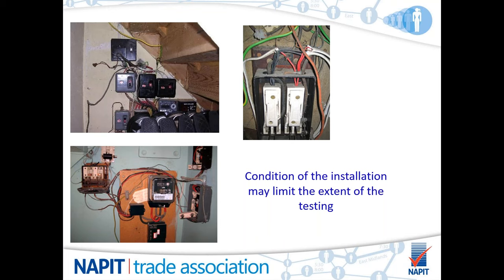Once again, the condition of the installation may limit the extent of the testing that you wish to carry out. As you can see from the pictures in this slide, the use of connector block for the installation, there's exposed conductive parts, like we spoke about before, meter tails have not been secured, which again could lead to loose connections and potential burning. And also, in the top right picture, we have potential for electromagnetic effects.